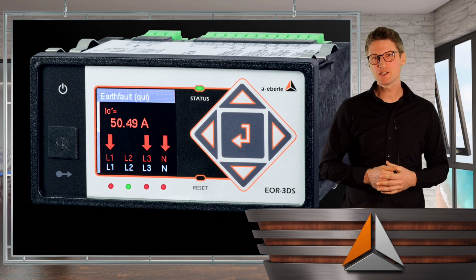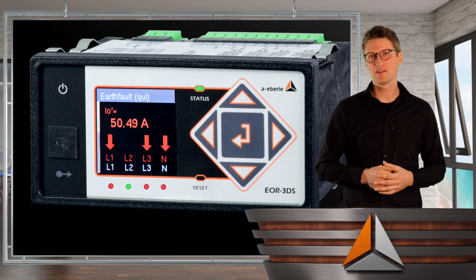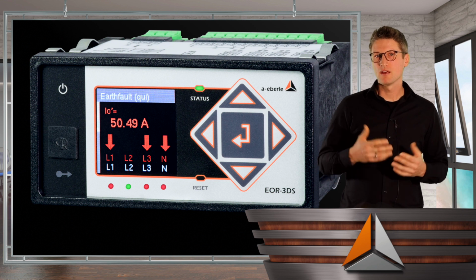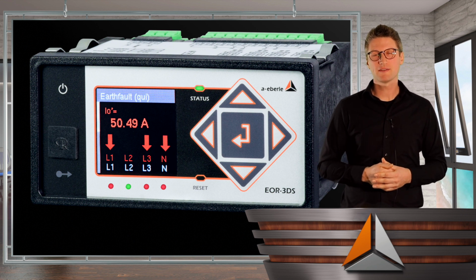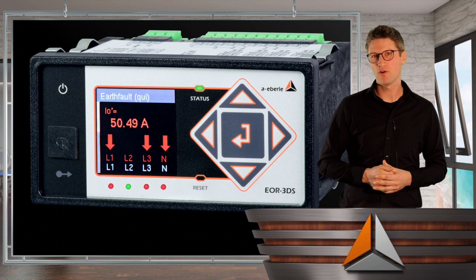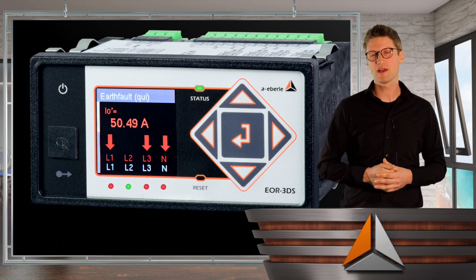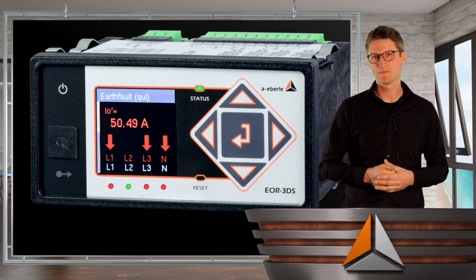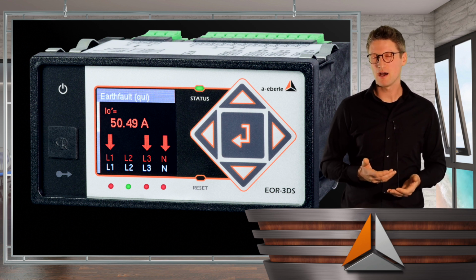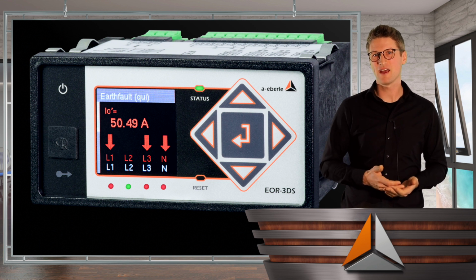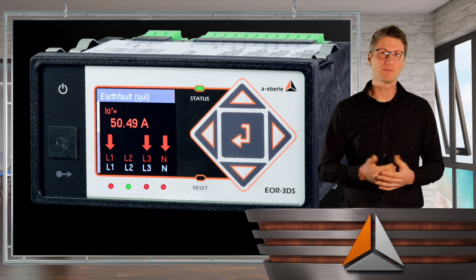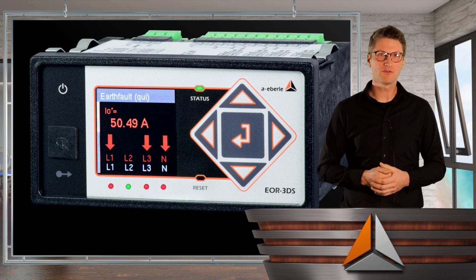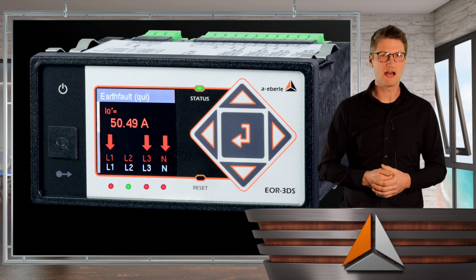The main features of the EOR-3DS, again in the overview. Of course, the EOR-3DS has some additional earth fault algorithms compared to the EOR1DS. So, for example, for reigniting earth faults. Fault records and logbooks are saved on SD card, and they are readable, for example, remotely via our software or via a central IoT software.